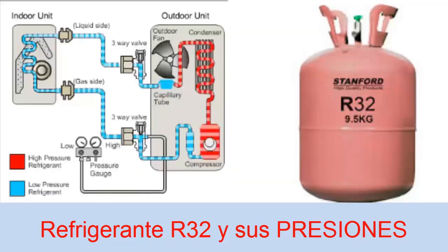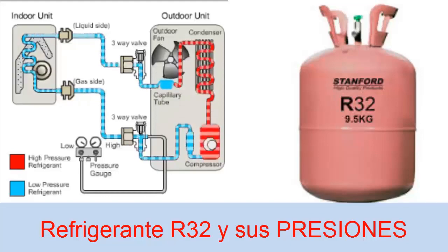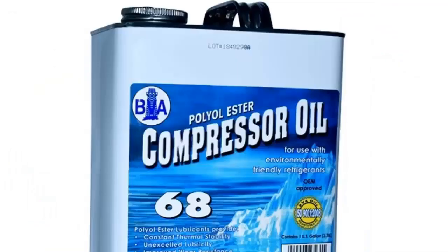For example, with POE 68 oil — which is the grade most commonly used with R410A and R32 — we can ensure that there is sufficient viscosity when the temperature is high. But in turn, when the temperature is low, it also flows properly.